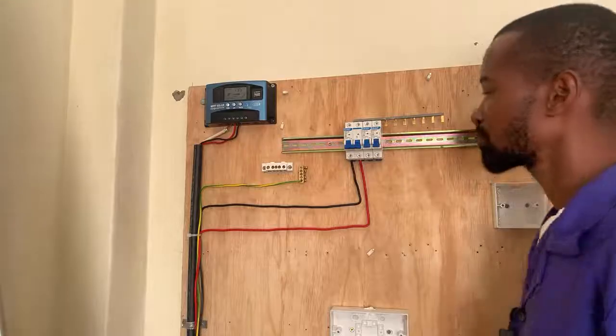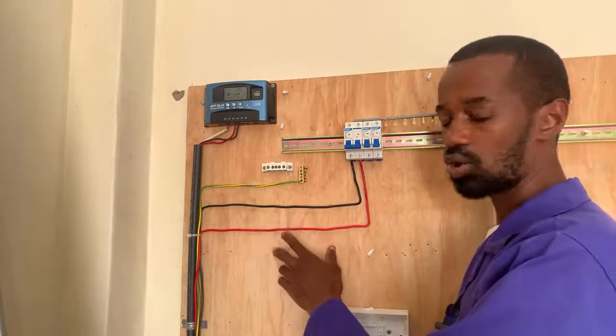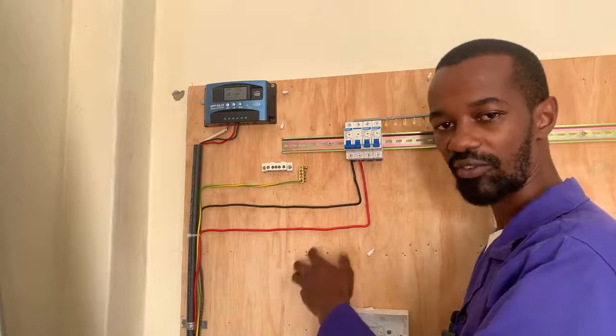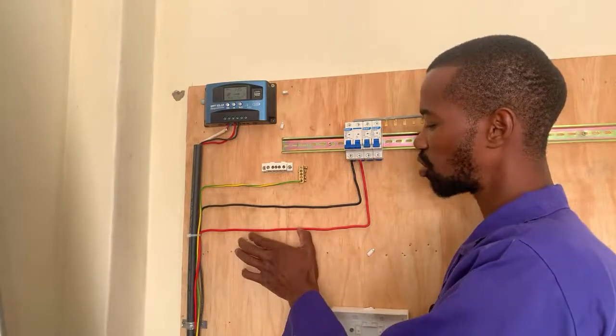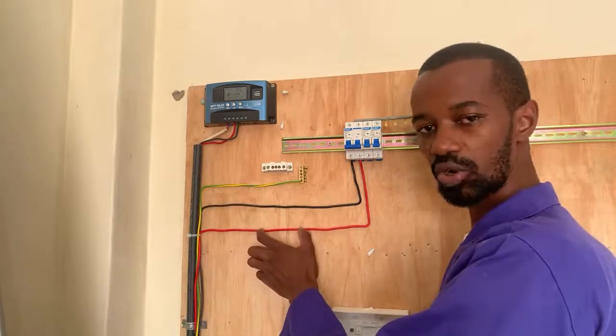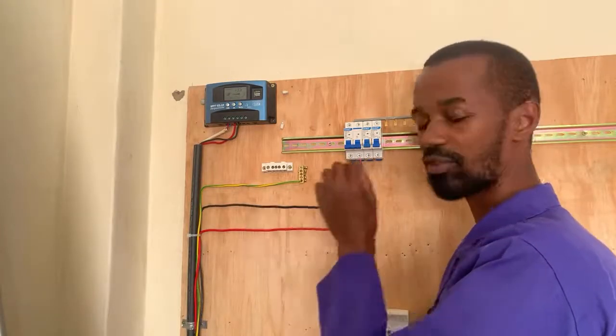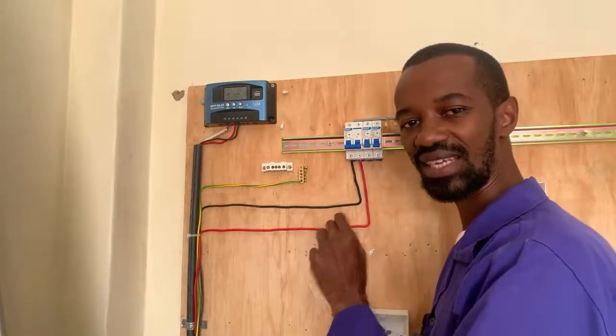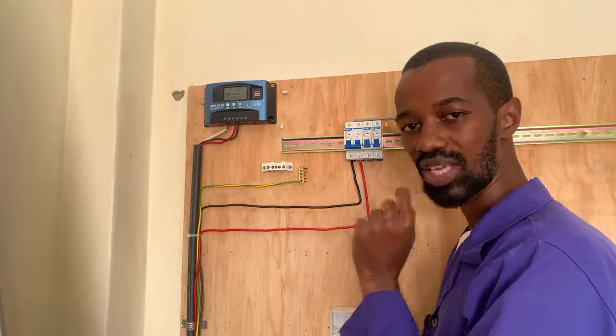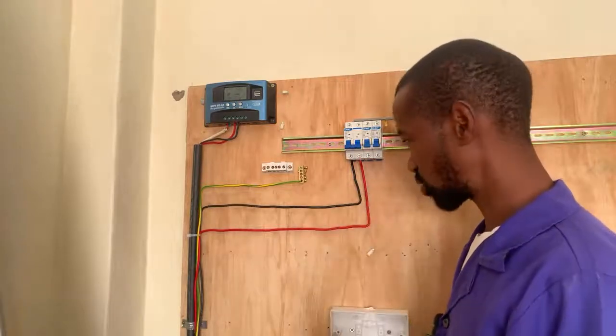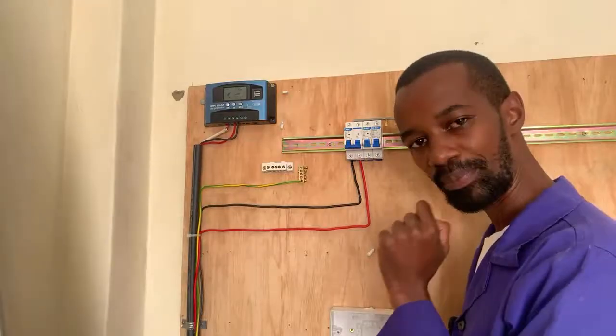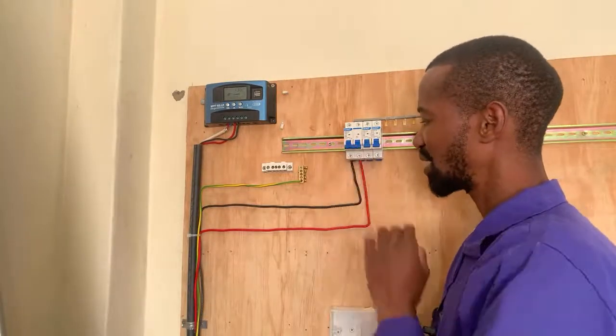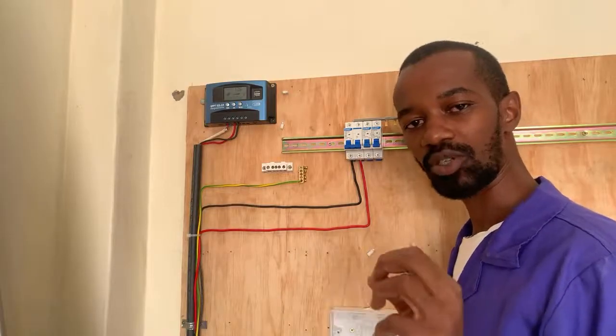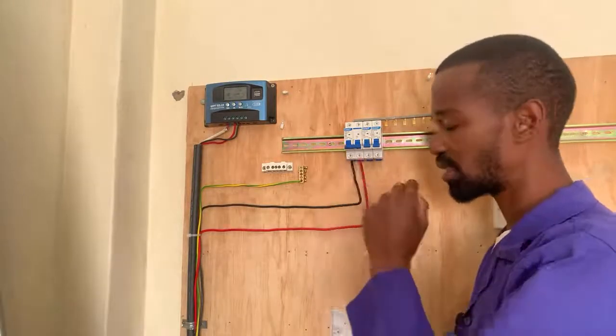surges. So that is, even at the transformer level, we have seen that normally the fuses are connected at the phase. For instance, you have a single phase transformer. The fuse is only placed at the phase connection, but the neutral comes all the way from the transformer to the conductor that is supplying the neutral to every installation. So the neutral is not supposed to be interrupted in any way, unless the phase is also part of the process of interruption, for instance, in this double pole switch.